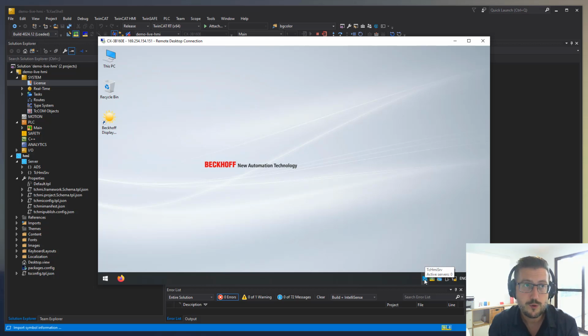1.10, this was just an executable you had to run. You had to run the server, and typically people put it in their Windows startup. In 1.12, it starts as a service. So if ever you need to stop TwinCAT HMI server, you can't shut it down just from this icon anymore. You have to go into Windows Services and stop the service. Okay, just so you've got that.